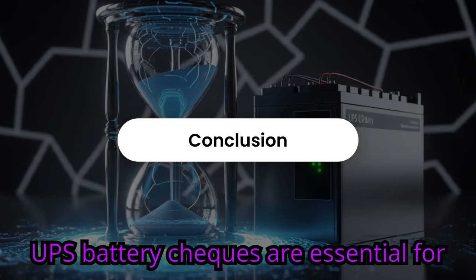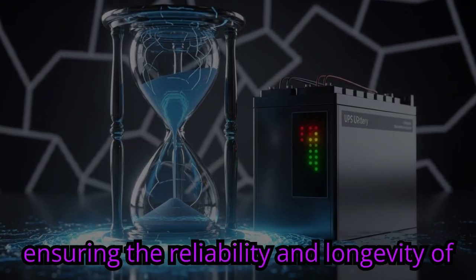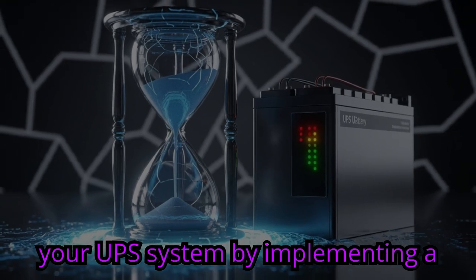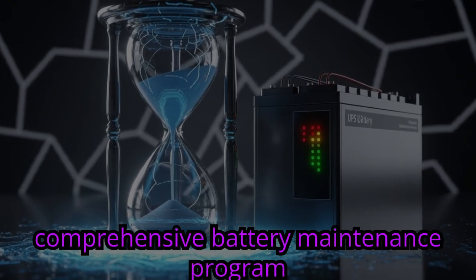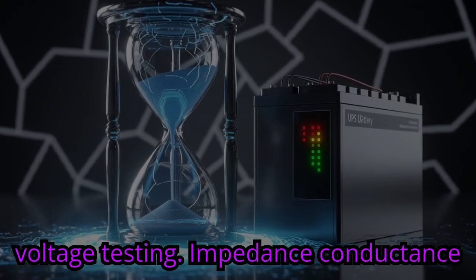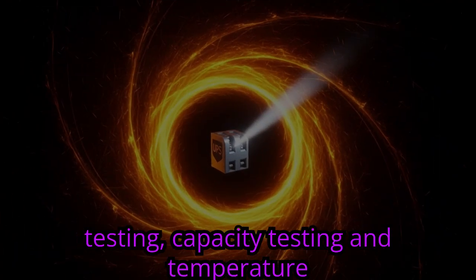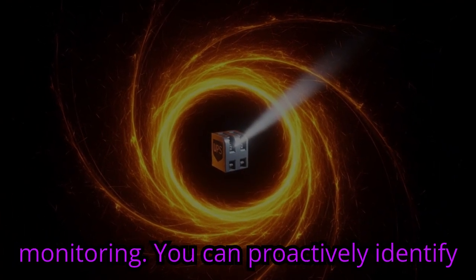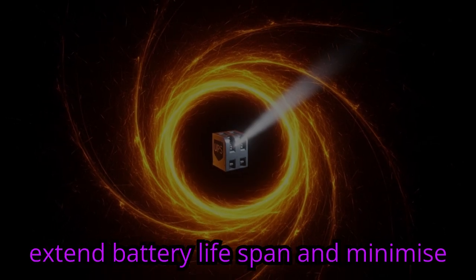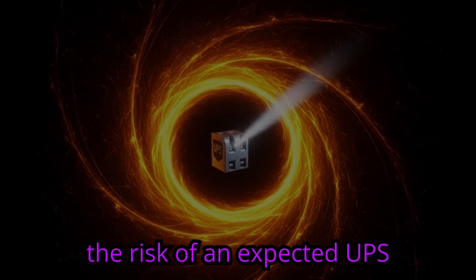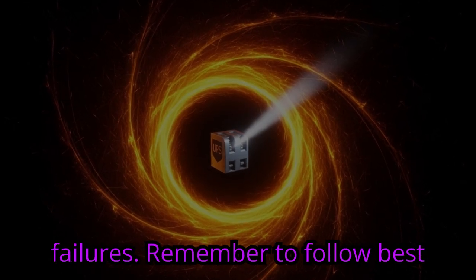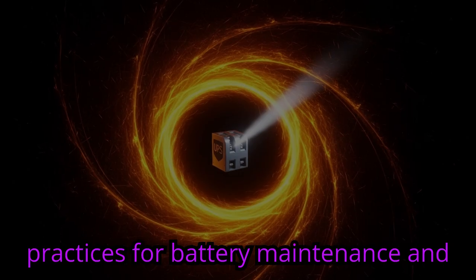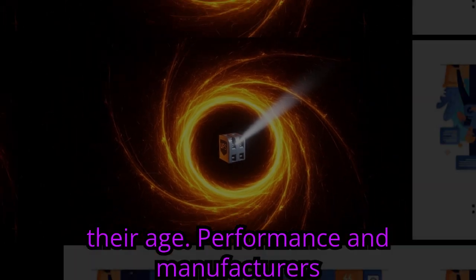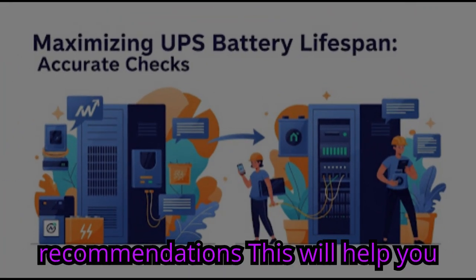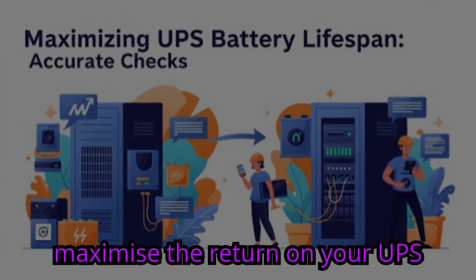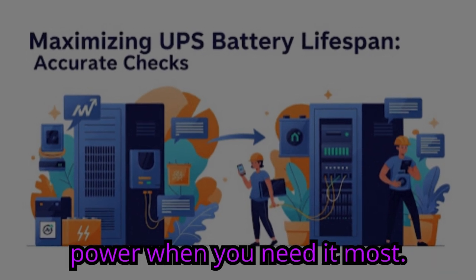Conclusion. Accurate UPS battery checks are essential for ensuring the reliability and longevity of your UPS system. By implementing a comprehensive battery maintenance program that includes regular visual inspections, voltage testing, impedance conductance testing, capacity testing, and temperature monitoring, you can proactively identify and address potential battery problems, extend battery lifespan, and minimize the risk of unexpected UPS failures. Remember to follow best practices for battery maintenance and replace batteries proactively based on their age, performance, and manufacturer's recommendations. This will help you maximize the return on your UPS investment and ensure reliable backup power when you need it most.